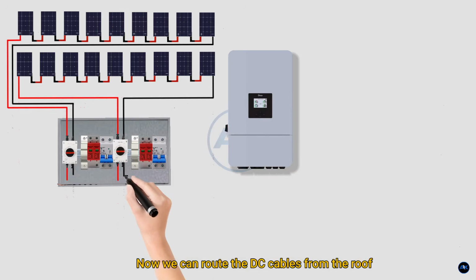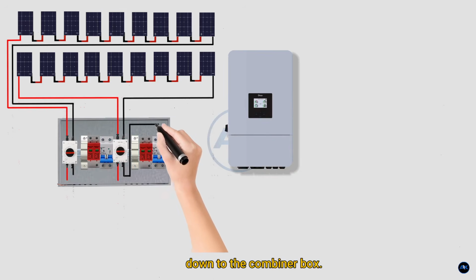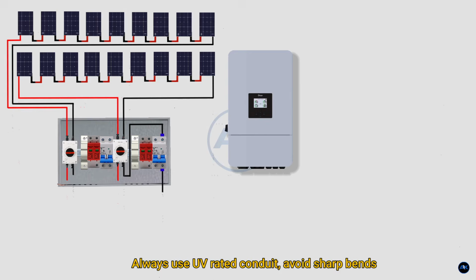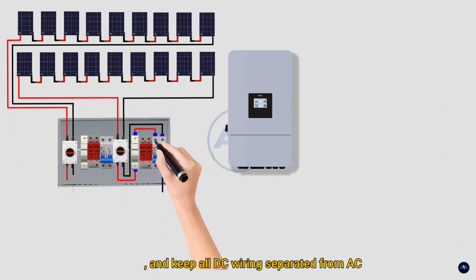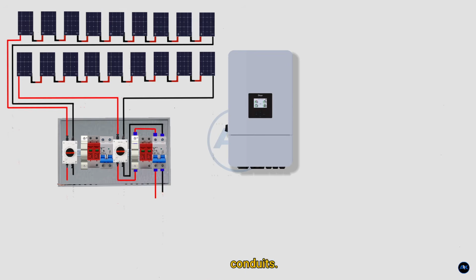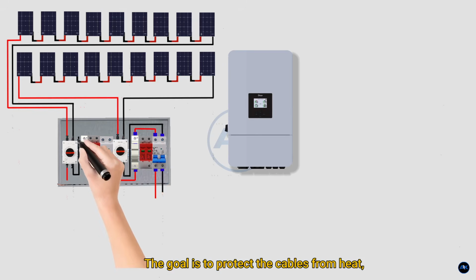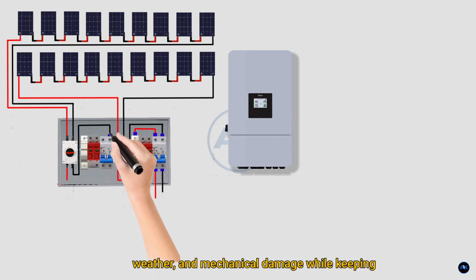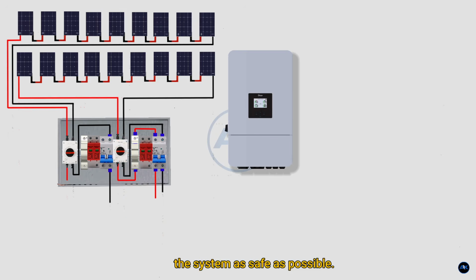Now we can route the DC cables from the roof down to the combiner box. Always use UV-rated conduit, avoid sharp bends, and keep all DC wiring separated from AC conduits. The goal is to protect the cables from heat, weather, and mechanical damage while keeping the system as safe as possible.